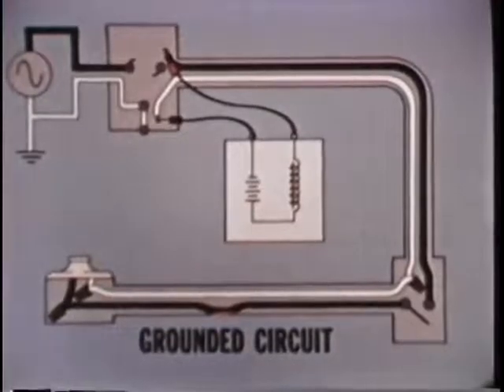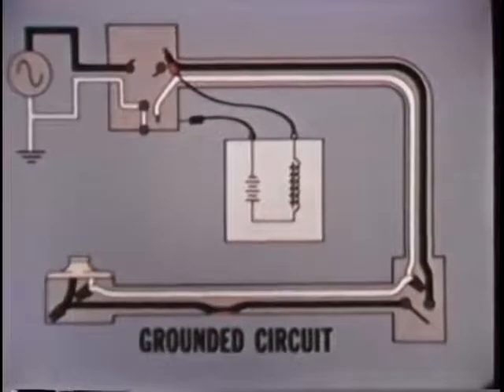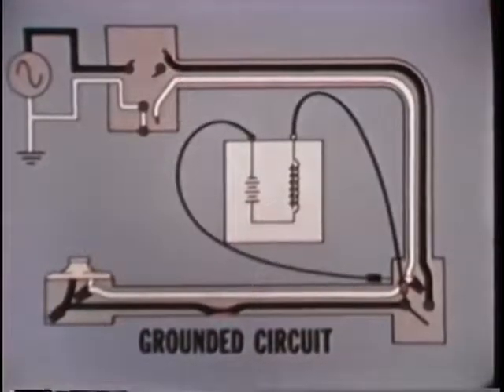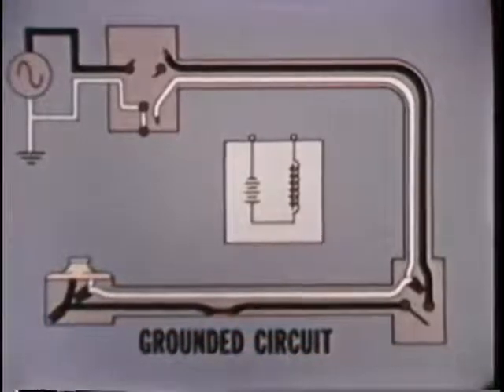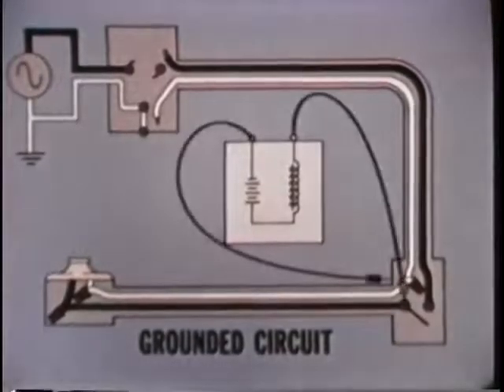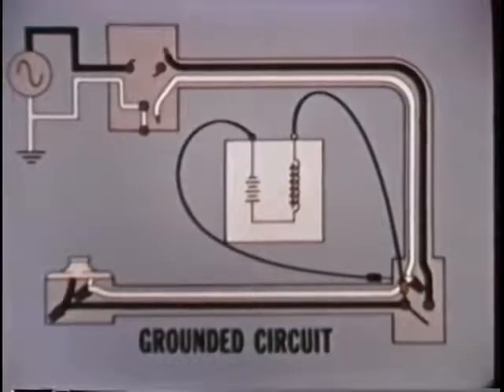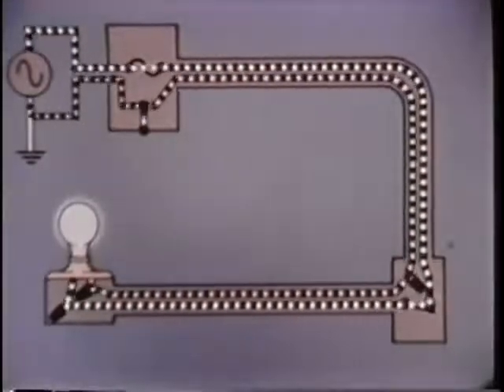First, checking between the two conductors indicates that there is no short circuit in the first section of the circuit. And there is no continuity between the hot conductor and ground in this section. However, between the hot conductor and ground in the second section, there is continuity. Since this is the last section, the testing is complete. In a longer circuit, the diagnosis would be confirmed by checking the next connection. The ground is removed and the circuit is retested at the trouble point, and all connections are restored. The light and fuse are replaced, and when the switch is turned on, the circuit is back in service.